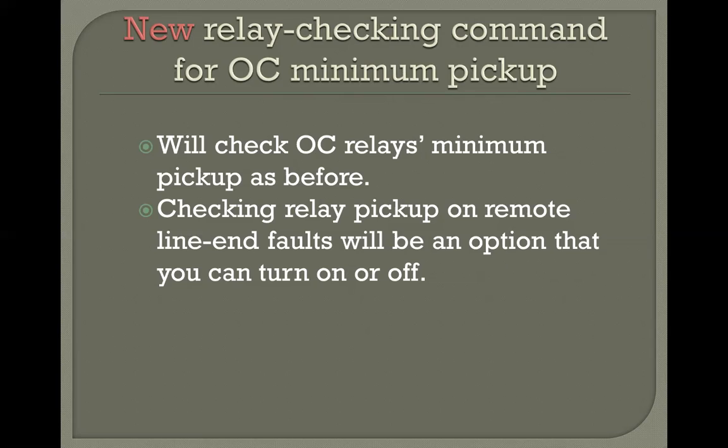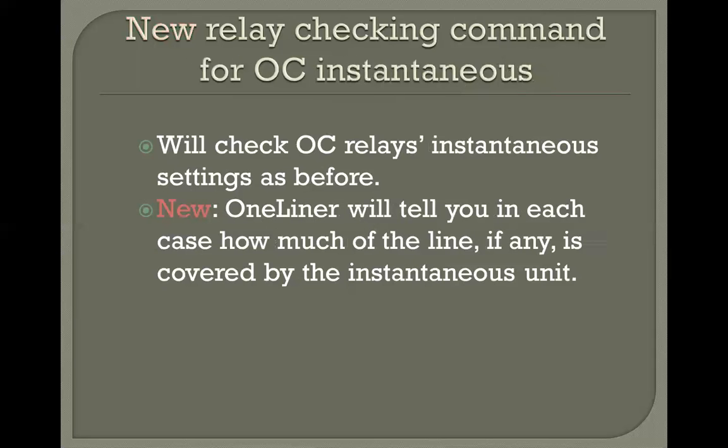Now in lower voltage systems, this might be important, but in high voltage there are still some overcurrent ground relays in use, for example, but people may not care whether it will trip on faults at the remote line end. So we made an option that you can turn this on or off. The relay checking command for overcurrent instantaneous is also more or less the same as before in terms of the algorithm.